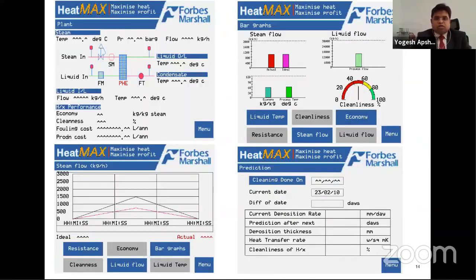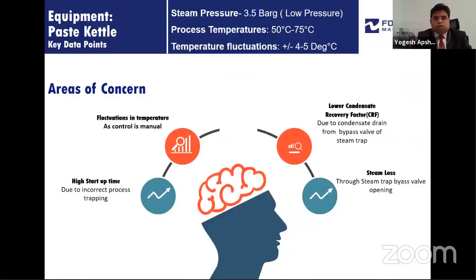So these are some of the mimics of the intelligent hot water systems. You would see that we can see the complete primary and the secondary side. If you see the steam in and steam out, we have a steam flow meter, temperature transmitters, and flow meters on the water sides. Then it gives you the ideal steam consumption, the actual steam consumption, and it also gives you the prediction for the fouling. So when you have to clean the gaskets or change the gaskets, we come to know about these dates much in advance. So this is the advantage.